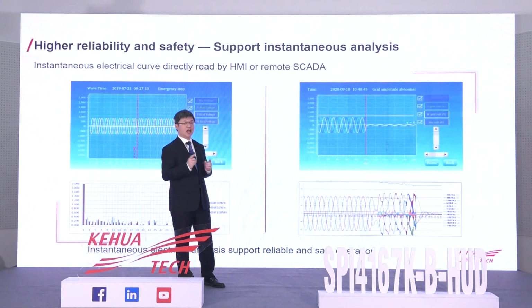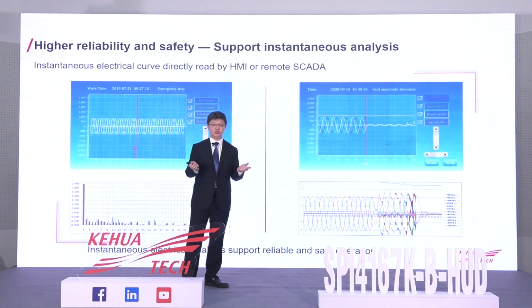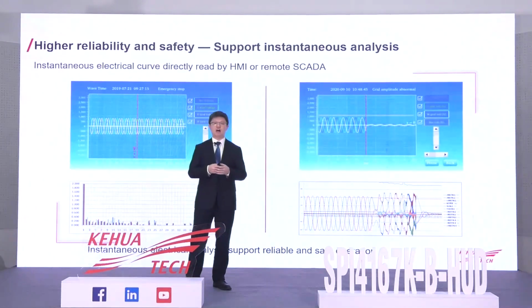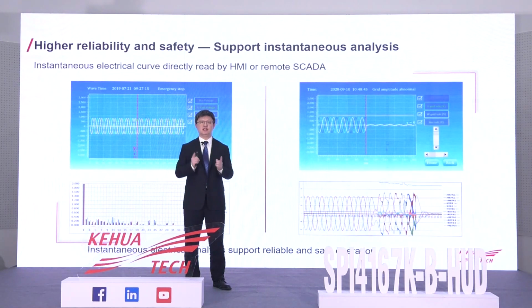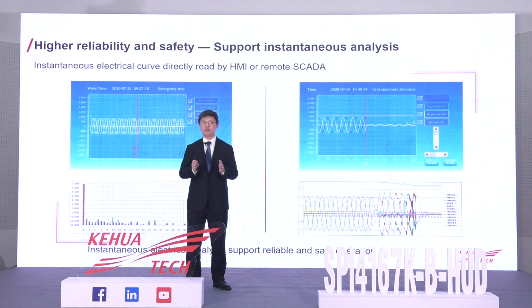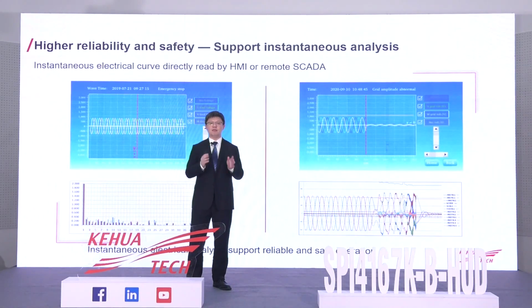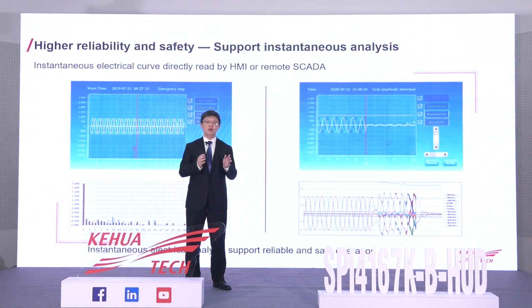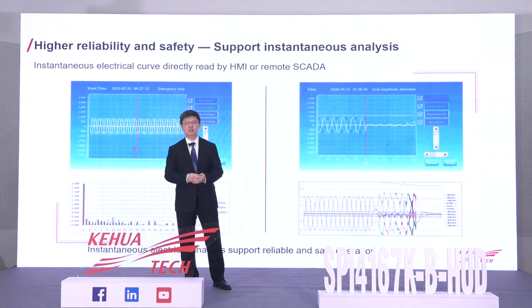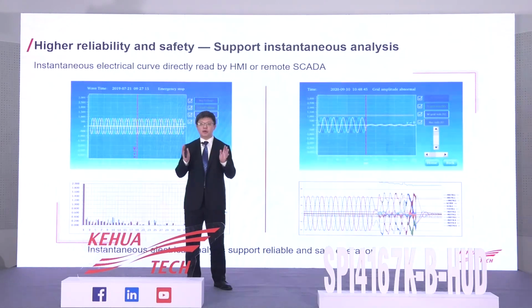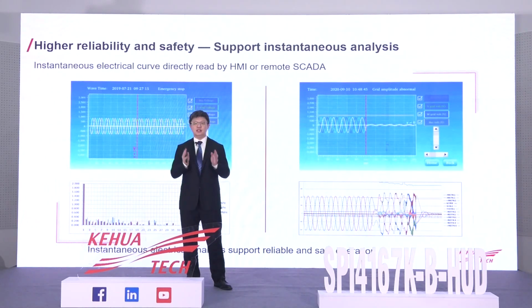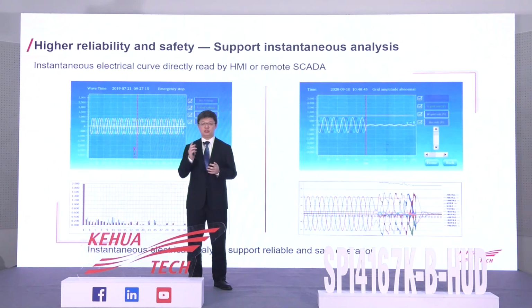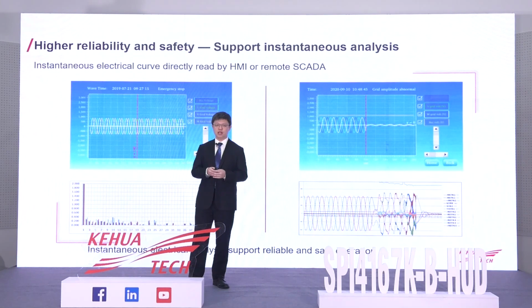Grid analysis can help the PV power plant optimize operation. Usually the SCADA of a power plant cannot observe the instantaneous status, for example when LVRT or HVRT happens. When harmonics grow, the O&M team has no records. So how can a power plant operate better without instantaneous electrical records? I believe recording function is very important to support reliable and safe operation.